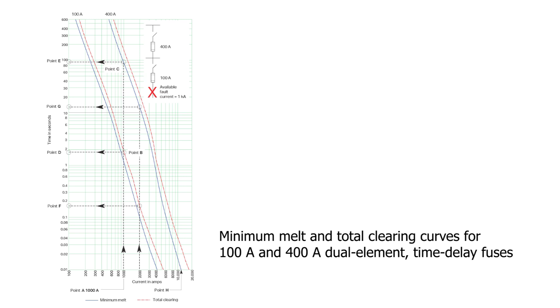and clear the circuit. Time current curves for fuses are primarily used to understand the opening time duration during overload or long time conditions. Fuses have an inverse time current characteristic, meaning the greater the overcurrent, the faster the fuse opens and interrupts.